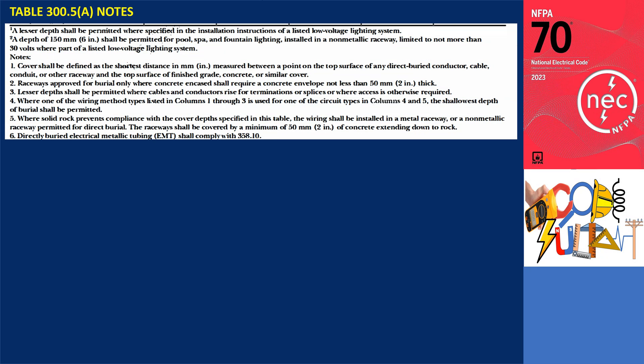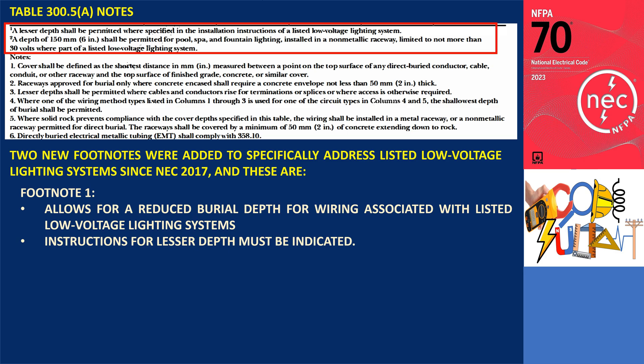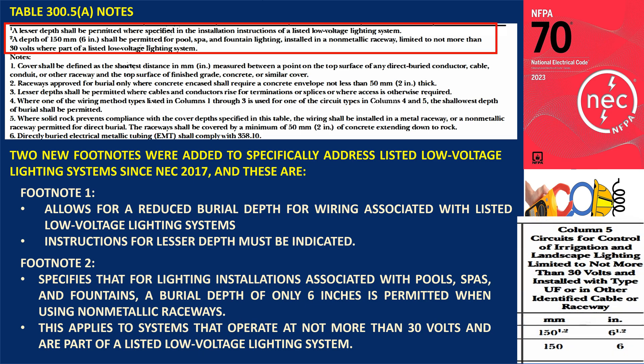We must also understand the notes below this table. Two new footnotes were added to address listed low-voltage lighting systems since NEC 2017. Footnote 1 allows for a reduced burial depth for wiring associated with listed low-voltage lighting systems, provided that the installation instructions for the specific system indicate a lesser depth. Footnote 2 specifies that for lighting installations associated with pools, spas, and fountains, a burial depth of only 6 inches is permitted when using non-metallic raceways. This applies to systems operating at not more than 30 volts that are part of a listed low-voltage lighting system. These footnotes apply to circuits in Column 5 — irrigation and landscape lighting limited to not more than 30 volts, installed with type UF or other identified cable or raceway.